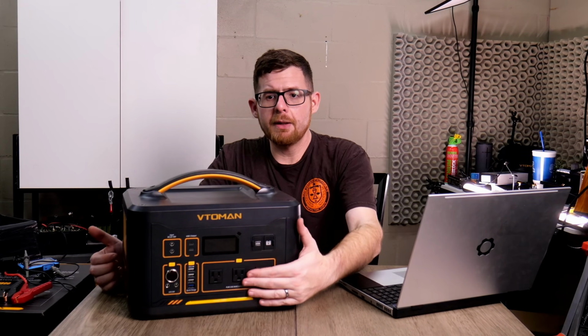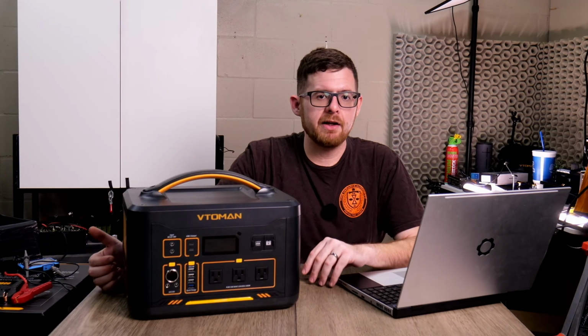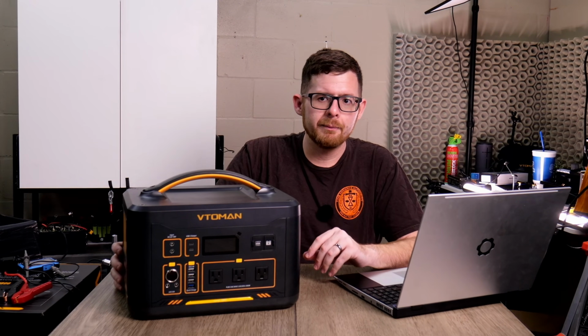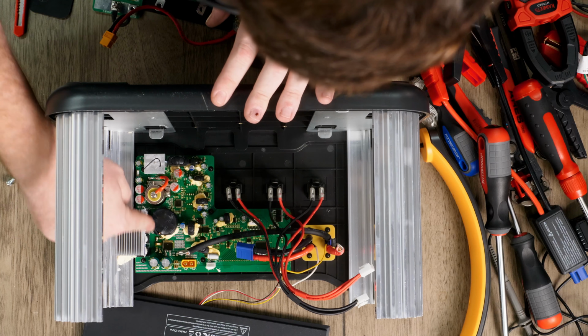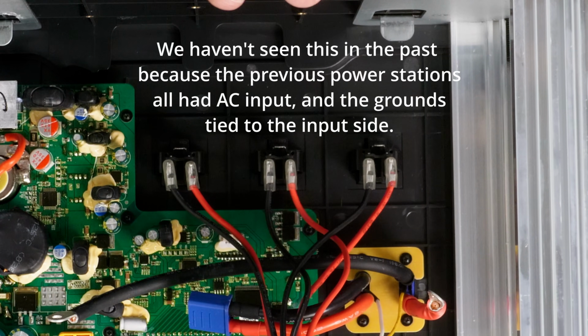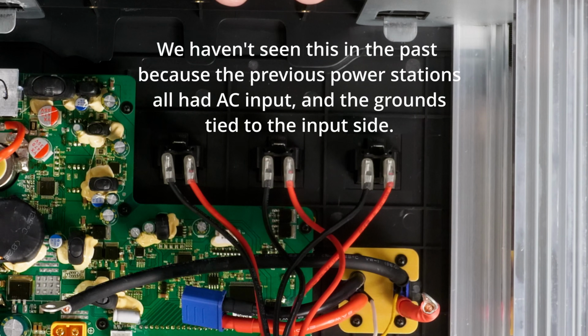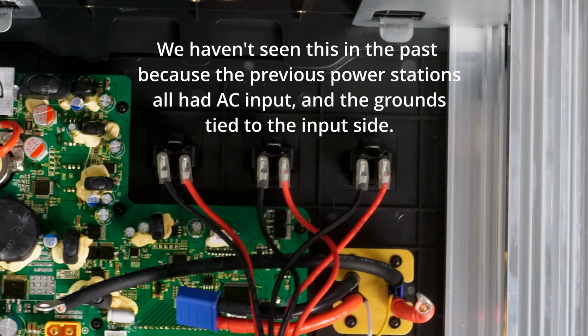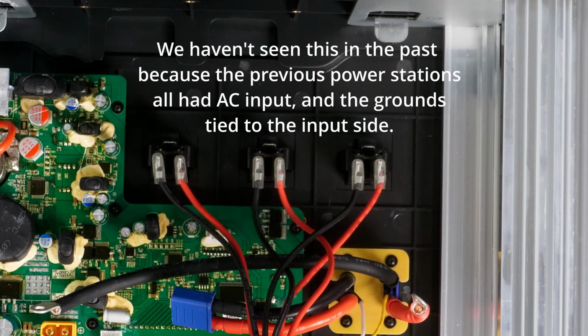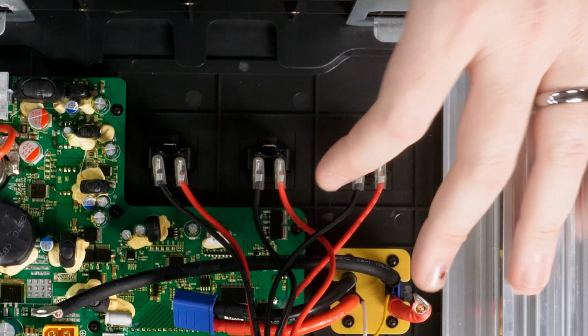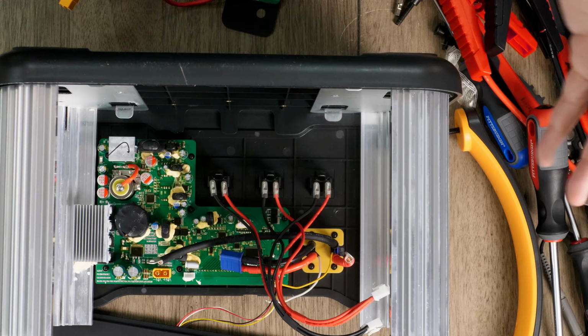Now, looking at these front panel connectors, the one thing I wanted to find out is why my neutral ground plug didn't work. And as you'll see here, unfortunately, the ground lines are not connected to anything. Not only are they not connected to each other, allowing a ground to potentially go across multiple devices, they're just floating out in air. So that is why our neutral ground bond didn't work.